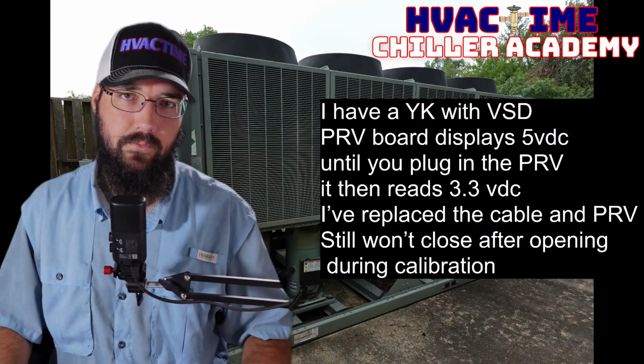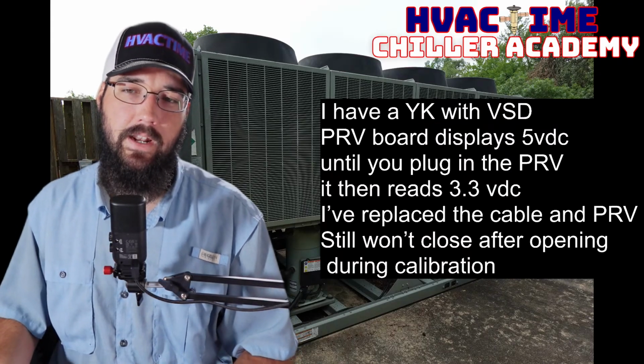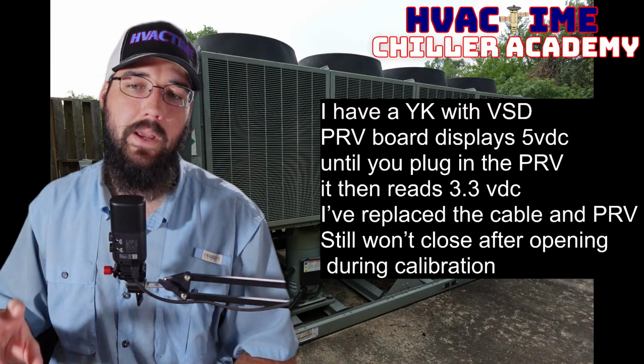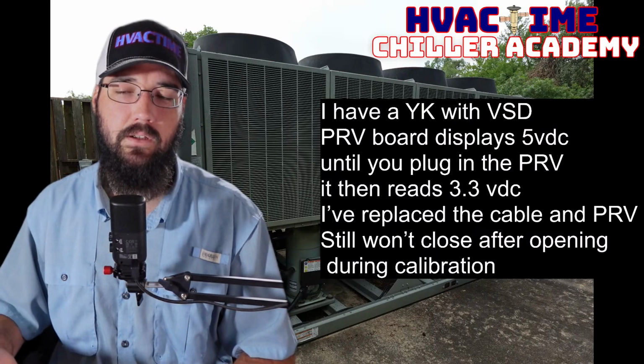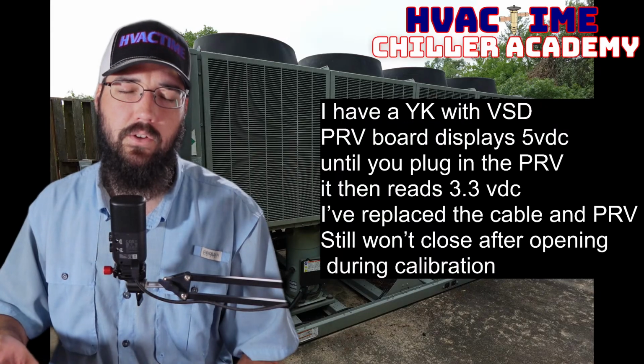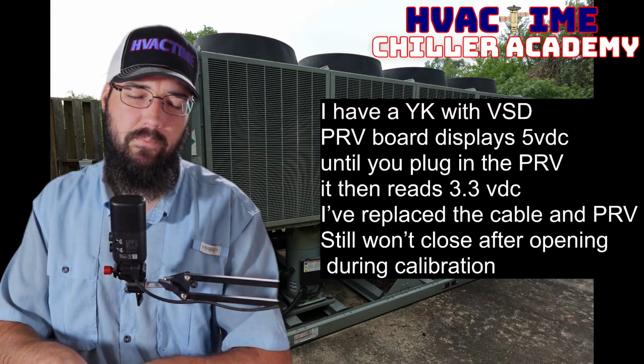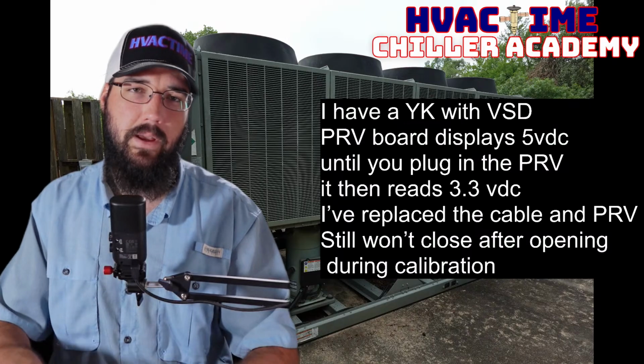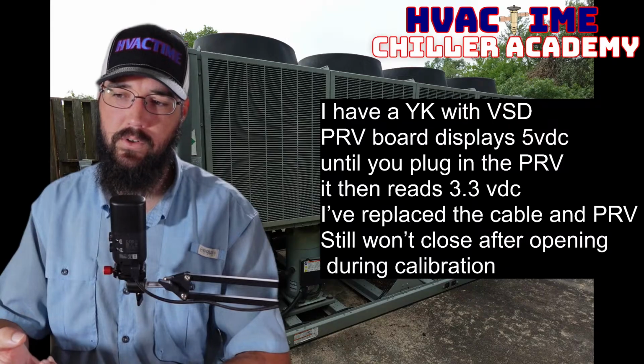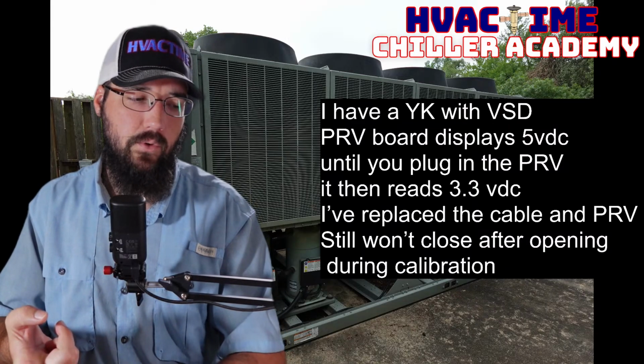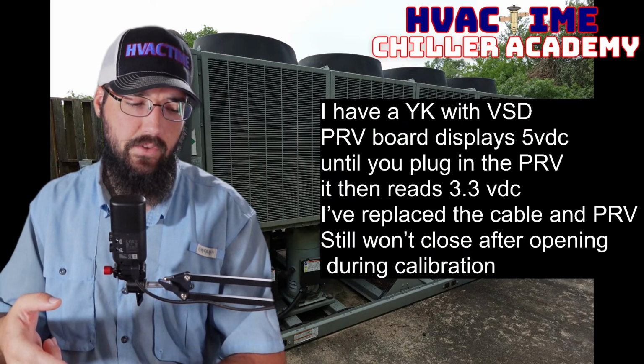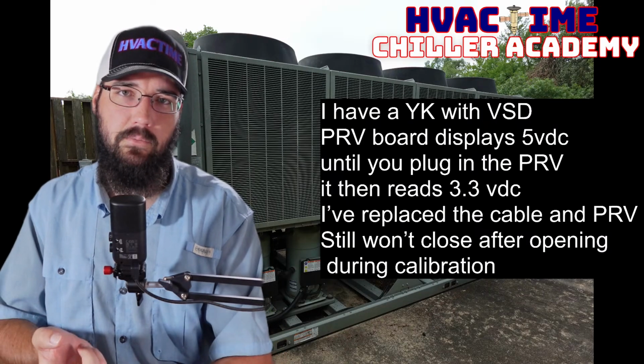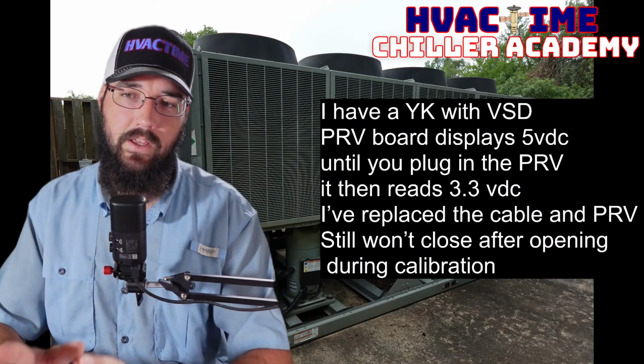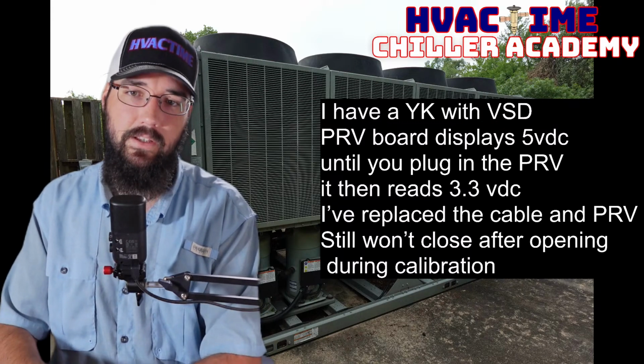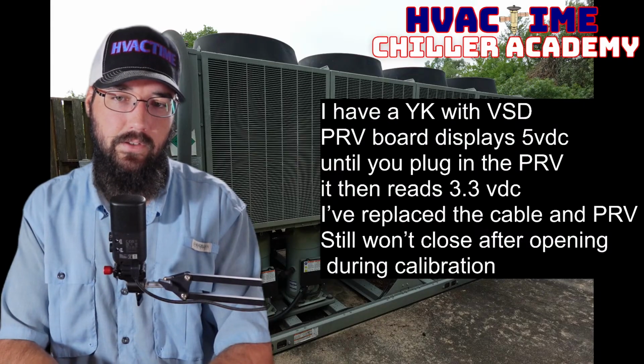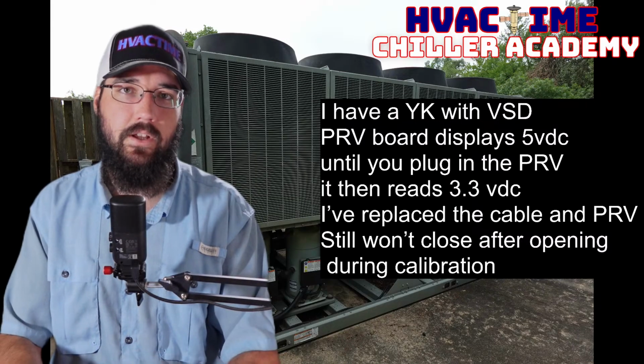My thoughts go in two directions. It could potentially be a board issue, and I don't remember without referencing the manual exactly what those voltages are supposed to be. The 5 VDC does sound right. I would need to reference the schematics and what you're actually working on, because I think part of that should be a 120 circuit and part of that should be a 24 volt circuit for the signals. The actuators I think are 120 or 24. Again, I've got to look back at the schematics, but if you're saying you've looked at the schematics and you're confident you should be maintaining 5 VDC, but then it goes to 3.3 VDC, you've replaced the cable and you've replaced the actuator, and it's still not doing what it's supposed to do.